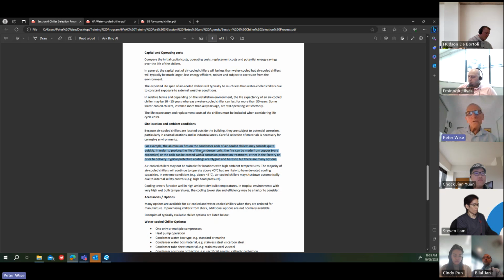Otherwise, the coils can be coated with a corrosion protection treatment, either in the factory or prior to delivery. Typical protective coatings are, these are brand names, Blygold and Heresite. You'll probably come across those. But there are many other options. So most chiller suppliers will have their preferred coating that they can offer you. And usually they'll include that when they quote you the chiller, because they know that most air-cooled chillers will require a protective coating.